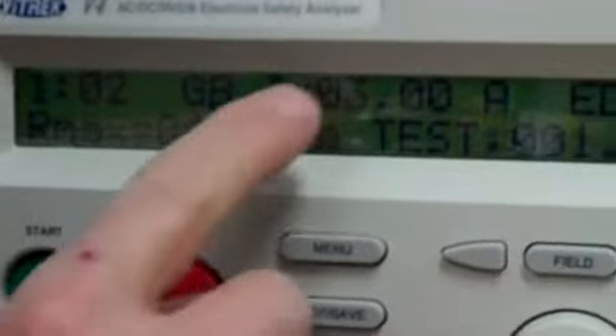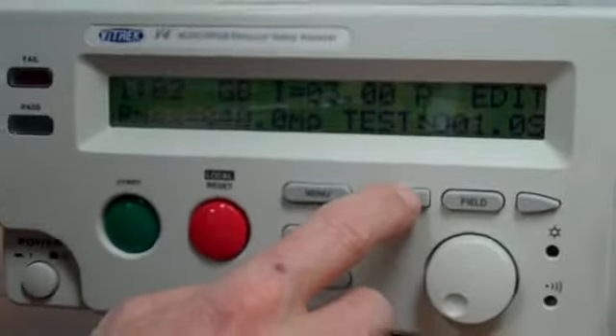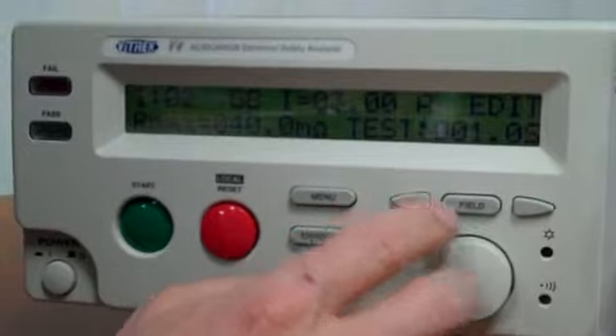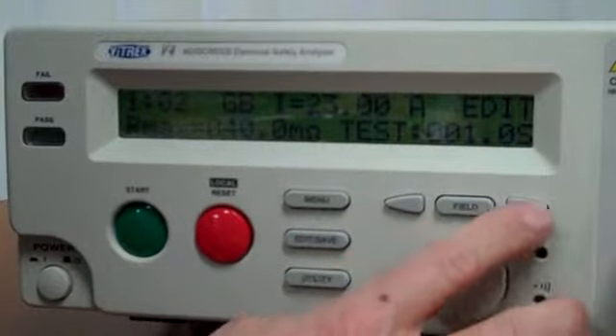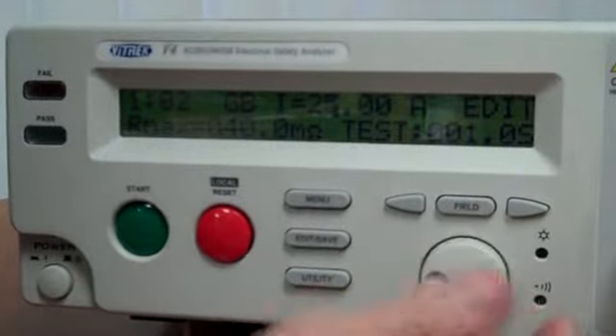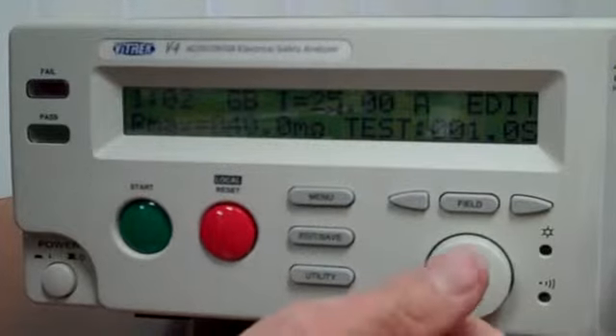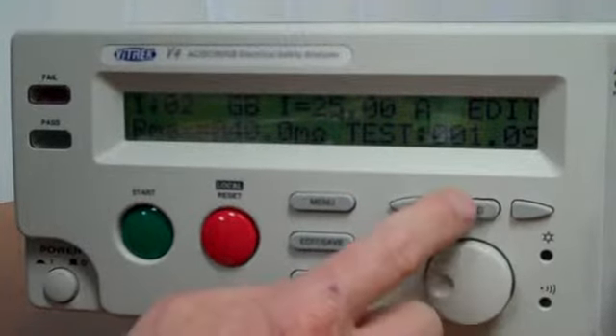Then I'm going to press the edit button, which takes me over into the parameter field, and we can scroll through and see the different functions. We're going to select ground bond. The test current is the next field, so I hit the field button and then cursor over to go to 25 amps. Very popular current for UL electrical safety testing on ground bond.